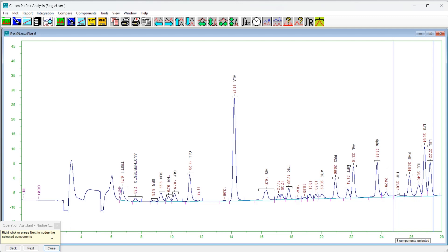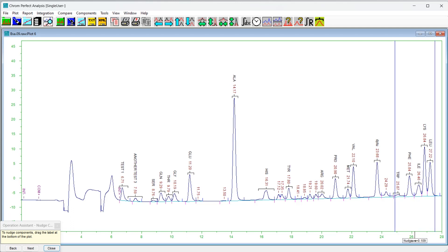Otherwise, the label will indicate the number of components and the region will snap to the selected components. To confirm the selection, either press the Next button on the operation assistant or right-click on the chromatogram plot. To adjust the position, click on the label and drag it horizontally; the vertical lines but not the search windows will follow the cursor. To confirm the movement, either press the Next button or right-click on the chromatogram plot. The chromatogram will be reintegrated and the search windows will be drawn in their new positions.